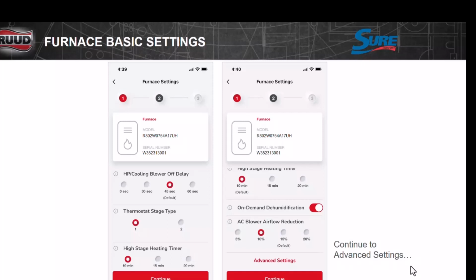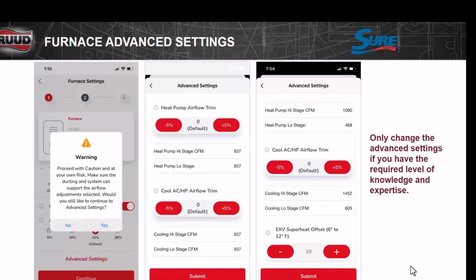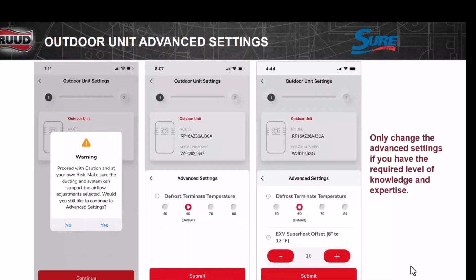Turn it to off. You can adjust the staging timer from 10, 15, 20 minutes to stage from high to low. And then we also have the trim features here. Outdoor settings, you can see defrost settings here. Defrost termination set at 60.